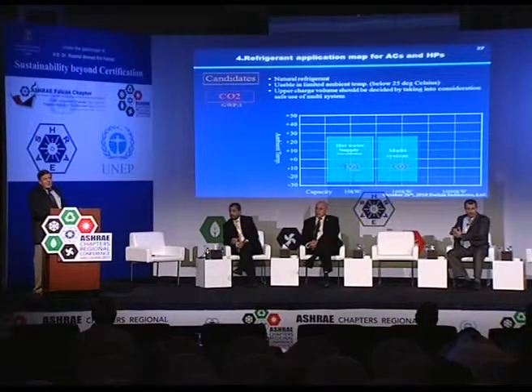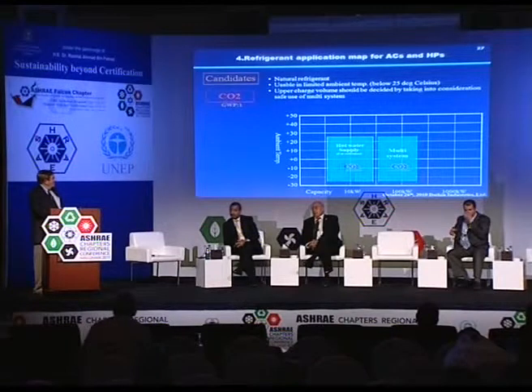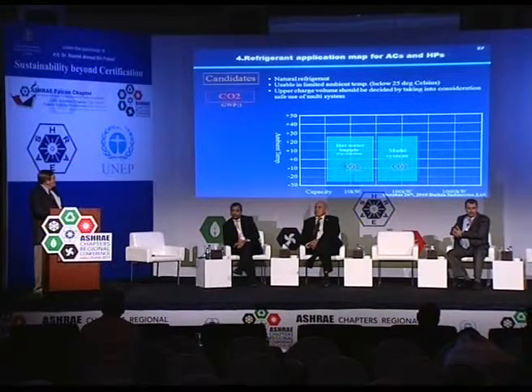CO2 becomes extremely limited, particularly in this area. If you look at where this chart lays off, you'll see we don't see CO2 used much above 25 degrees C condensing temperature. In this part of the world, condensing temperatures would be way above that. One of the problems with CO2, besides efficiency, is the cost of the product because of the pressures at these increased temperatures would be basically prohibitive.